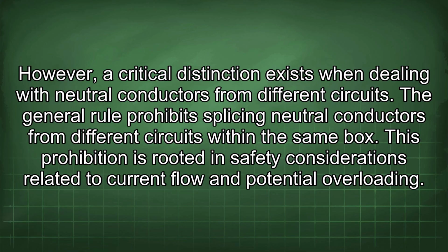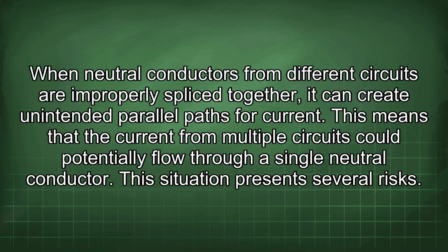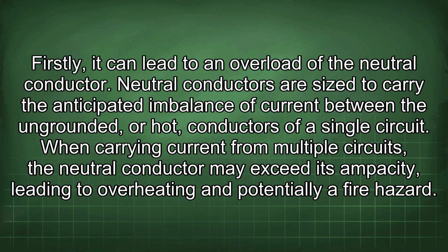A general rule prohibits splicing neutral conductors from different circuits within the same box. This prohibition is rooted in safety considerations related to current flow and potential overloading. When neutral conductors from different circuits are improperly spliced together, it can create unintended parallel paths for current. This means that the current from multiple circuits could potentially flow through a single neutral conductor. This situation presents several risks. Firstly, it can lead to an overload of the neutral conductor.